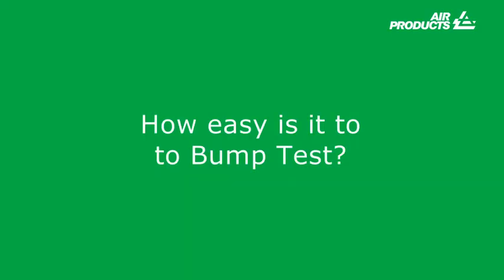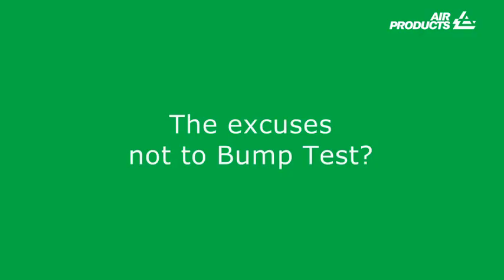How easy is it to bump test? The simple answer is very easy. A typical bump test should take no longer than 20 seconds. With ever-advancing technology in instrument and docking station design and increasing availability of gas mixtures, bump testing for many sensors is now possible. A manual bump test is also an option if the docking station is not available. There is no excuse not to bump test. The excuses not to bump test?